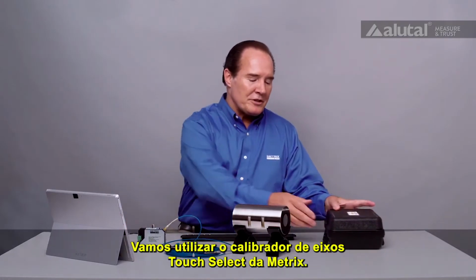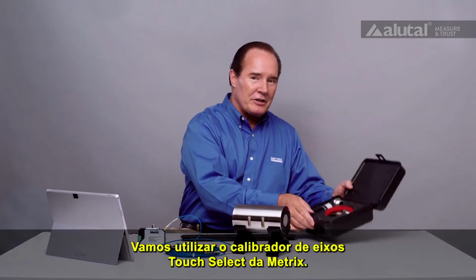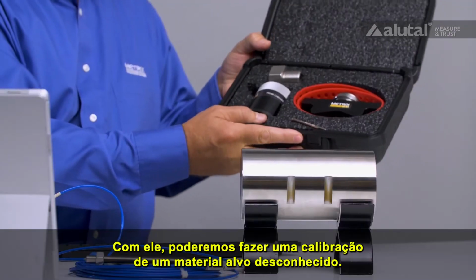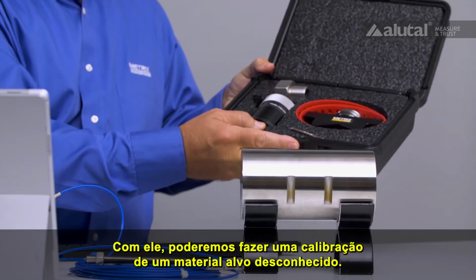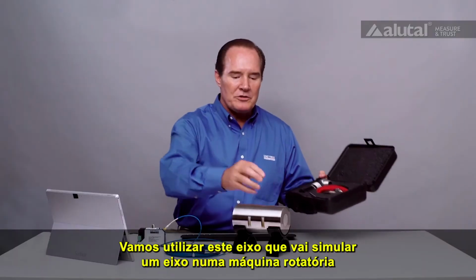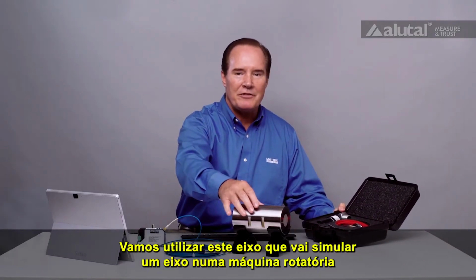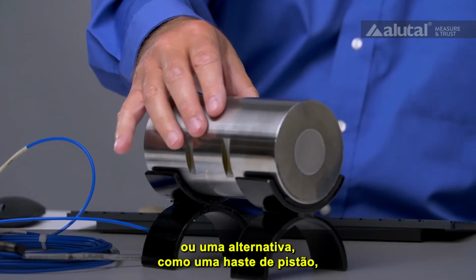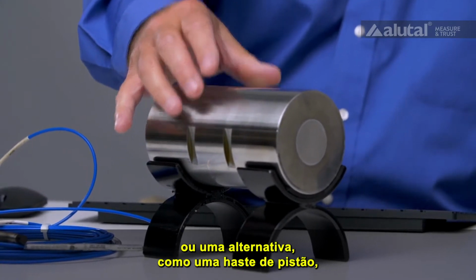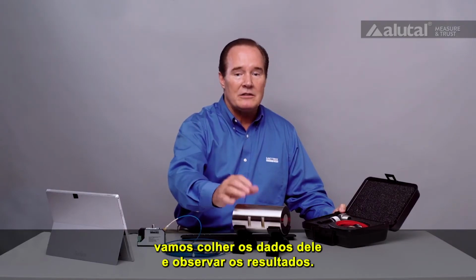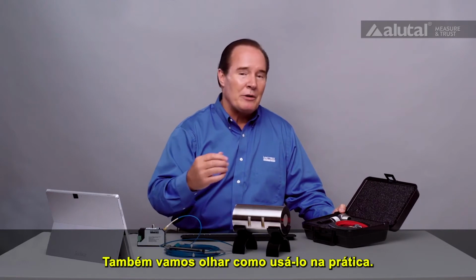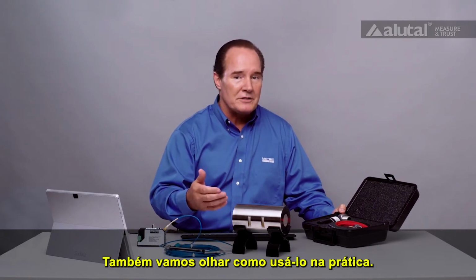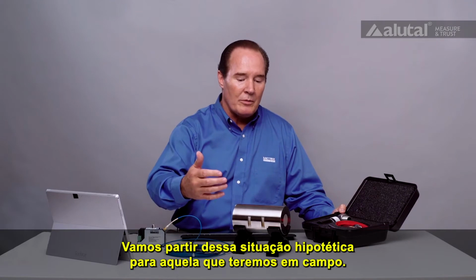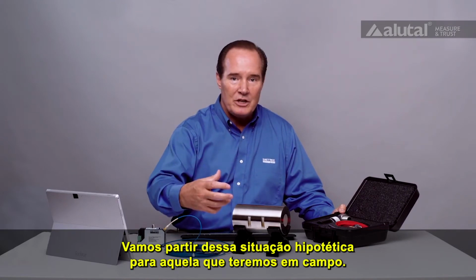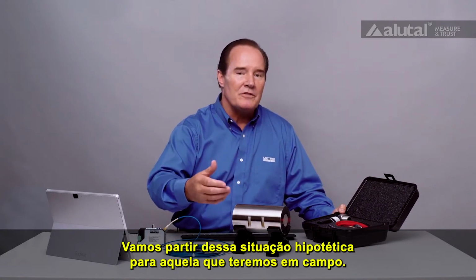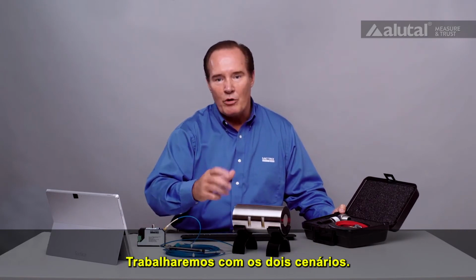We're going to use the Metrix shaft calibrator touch select, which is a way that we can get a calibration on an unknown target material. So we're going to use this shaft that will simulate a shaft in a rotating machine or a reciprocating machine like a piston rod, and we'll take readings on it and look at our results, and we'll also look at how you'd use this in practice. So we'll be going from the classroom situation that we have here to what we see in the field, and so we'll be discussing both those scenarios.